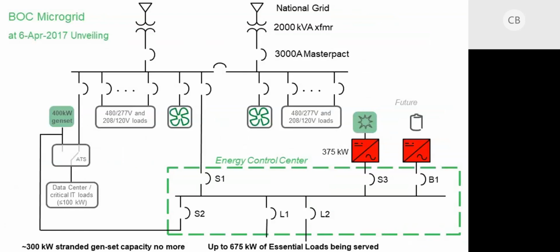So here we installed a microgrid solution, and you can see in the bottom right there's this energy control center, and Karsten explained that. This control center allows you to connect these other distributed energy resources, and it has this Microgrid Advisor software in there that will make intelligent decisions as to when you should use these other distributed resources. So we had 375 kW of solar power tied to that, and then we also installed at a future date 125 kW of battery power. So between the generator, we had an excess of 300 kW of capacity on the left.